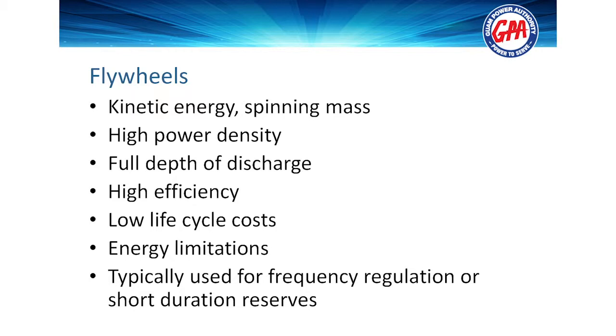Flywheels, kinetic energy, spinning mass. In the old days, what a flywheel was, you would take something like a big motor, put a big weight on it, connect it to the power system, and that's your flywheel. So your flywheel would essentially be an old generator or something that you put a big weight on, and that big weight is what kept the system from changing from 60 hertz. All a flywheel is, is inertia. If you have a motor turning at a certain RPM, that motor turns at the same speed as your power system. So if your power system's spinning at 60 hertz, your motor turns at 60 hertz. If your power system all of a sudden goes to 59 hertz, your motor, because it's a big weight, doesn't change to 59 hertz. It still tries to spin at 60 hertz. Since it's still trying to spin at 60 hertz, it helps prop up the power system. That's really all a flywheel is.